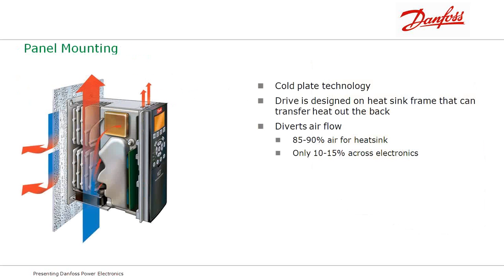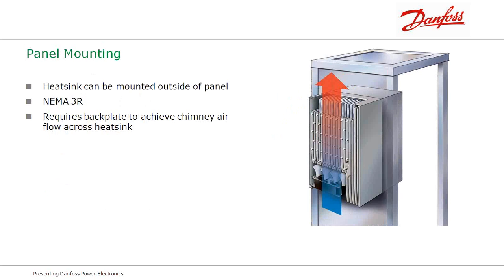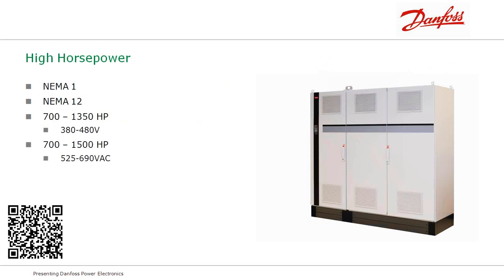You move all your big volume of air and your heat out, and then your electronics stay cooler with different airflows into there. So that allows you to isolate the hydrogen sulfide gas and impurities that we see in the air in our market. Part of that also allows you to mount the heat sinks out the back to get the heat out of the panels. A lot of innovative technologies in that, again, keeping the 85% of the heat out of the unit.